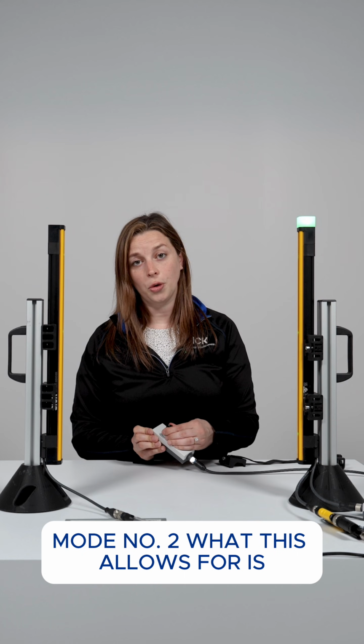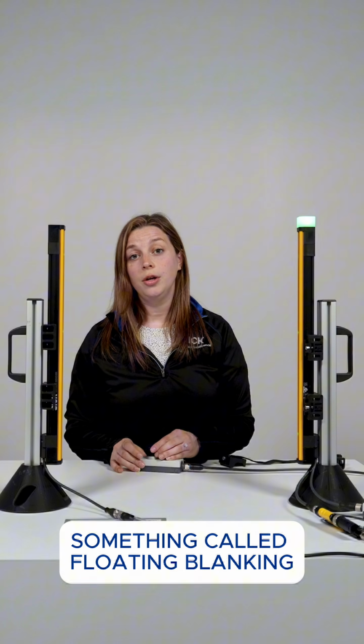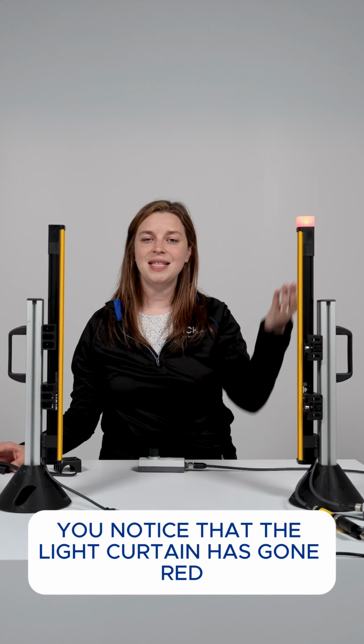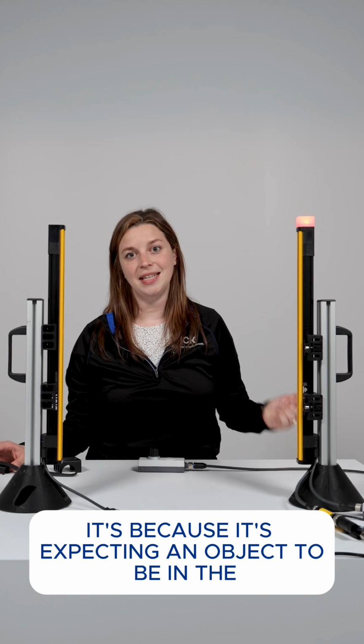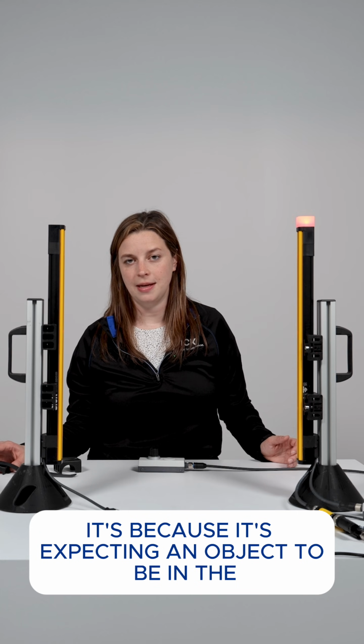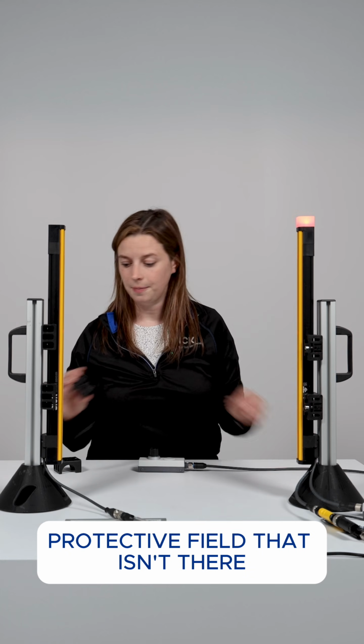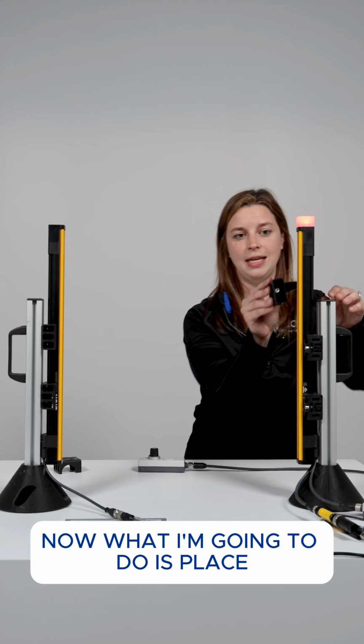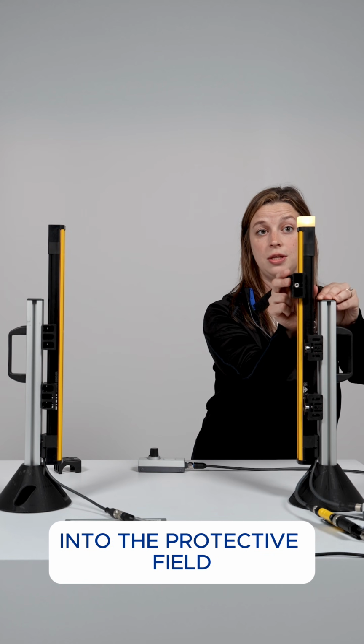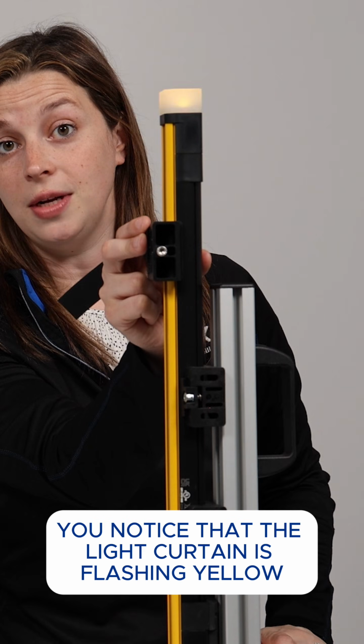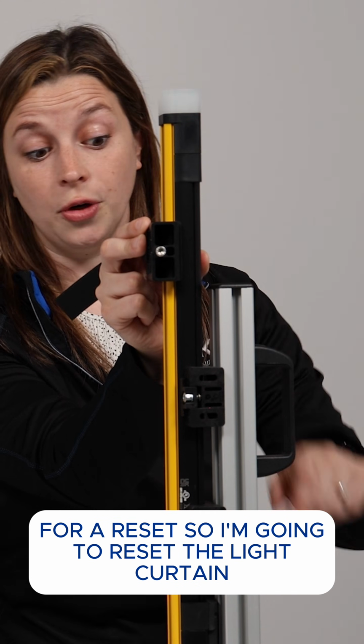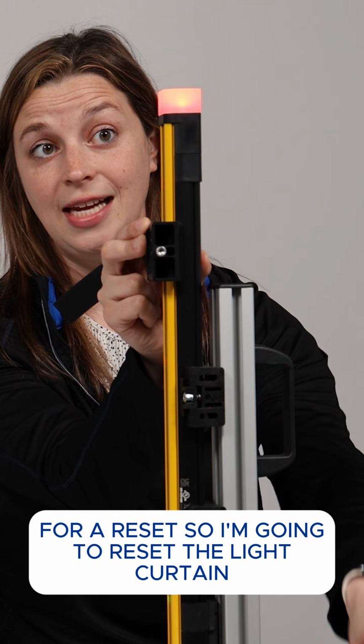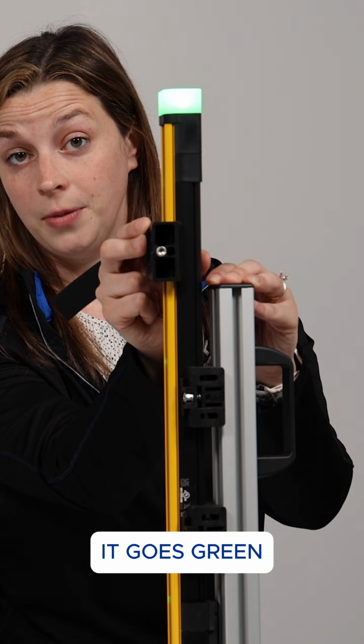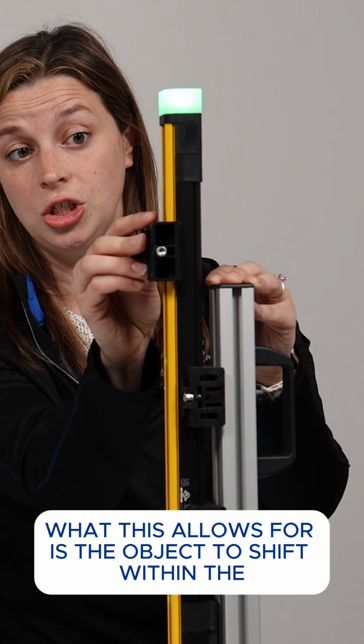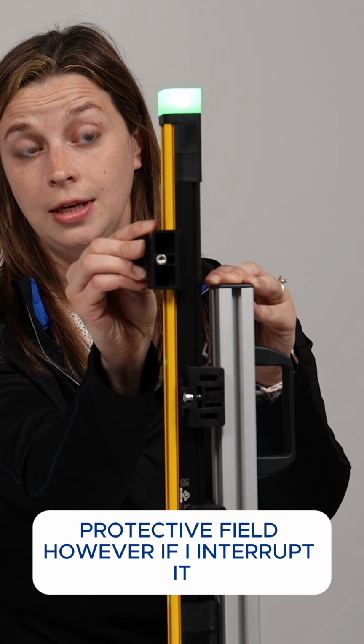The next function I'm going to do is switch to mode number 2. What this allows for is something called floating blanking. You notice that the light curtain has gone red. It's because it's expecting an object to be in the protective field that isn't there. Now what I'm going to do is place my floating blanking object into the protective field. You notice that the light curtain is flashing yellow for a reset, so I'm going to reset the light curtain. It goes green.